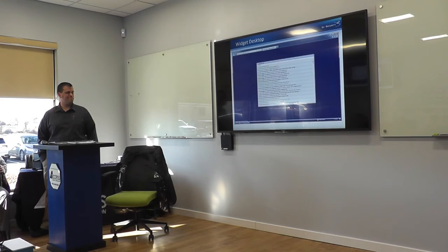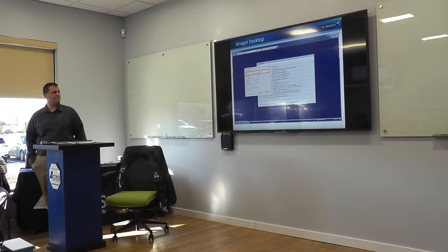The Compose Properties panel presents a number of options that modify the appearance and operation of the widget. The title field allows you to designate the text that appears at the top of the activity log widget. The next 4 checkboxes are used to allow the user of the widget desktop to close, minimize, move, or resize the widget. If there are multiple partitions on the controller you are monitoring, you can click the Allow Multiple Partitions Viewing checkbox to give the user the ability to monitor all partitions. A useful option on this screen is Allow Filtering.